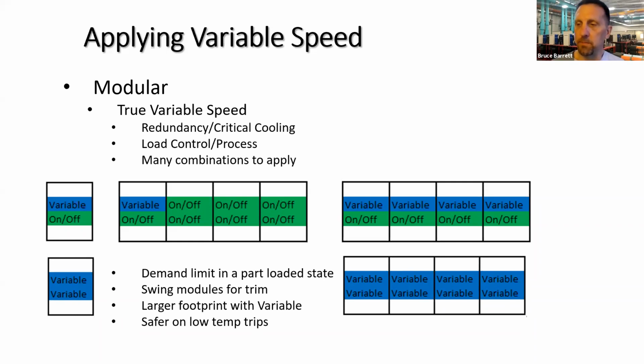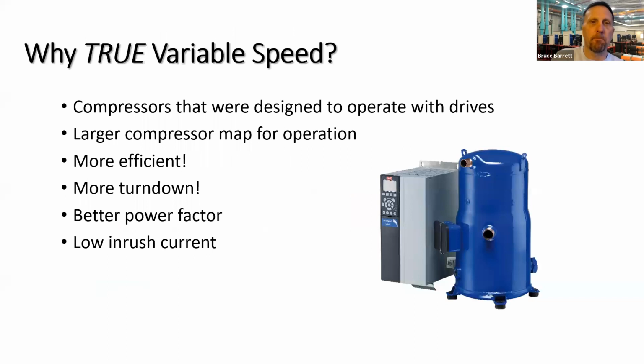I do believe with that variable speed compressor, you've got some excellent bonuses. The lowest inrush possible, having all variable speed. These do have direct driven motors. They have qualities of harmonics that are very good for applications where there are critical components shared on the electrical system. It's a great option. You don't have to go on-off scrolls. You can blend or go all in on true variable speed. It's just more efficient, better turn down, power factor, low inrush. There's a lot of benefits.